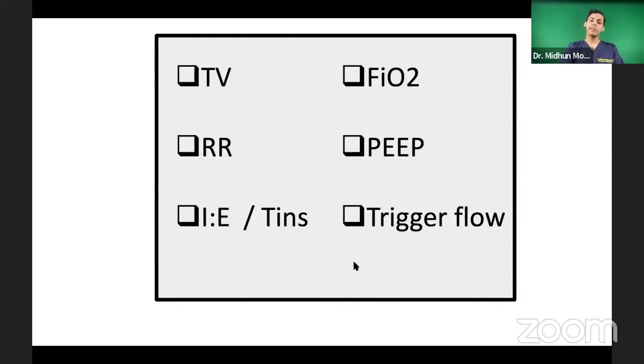All right. But in some ventilators, you have the option of setting only the time for inspiration. So if you are having 3 seconds for a breath, you set it as 1 second for inspiration. So obviously the remaining 2 seconds will be used for expiration. So now you have taken care of the breathing part, the ventilation part, how to give the breath to the patient.